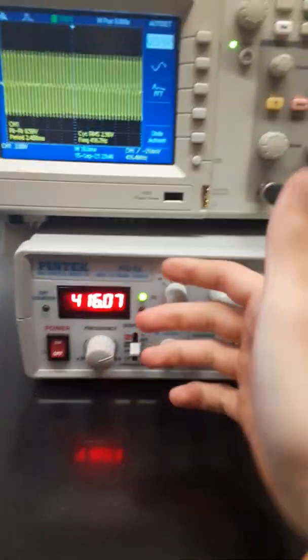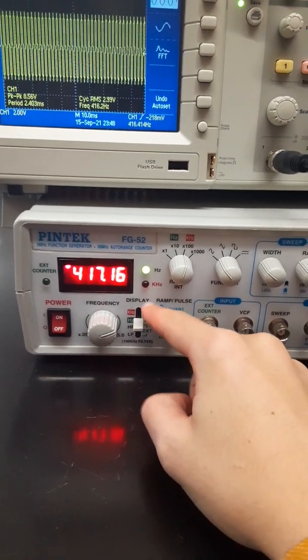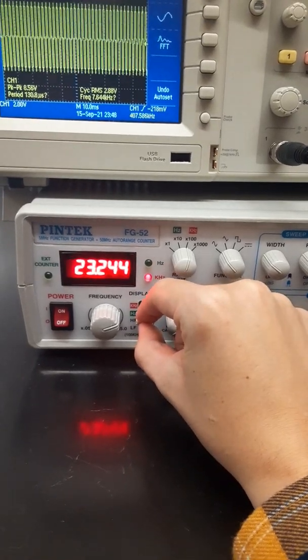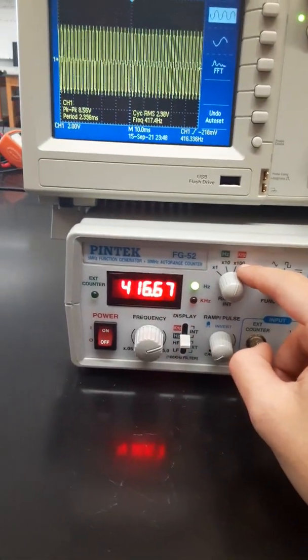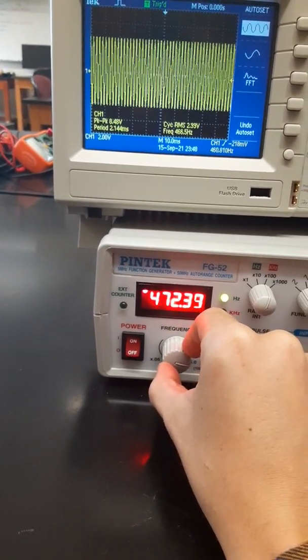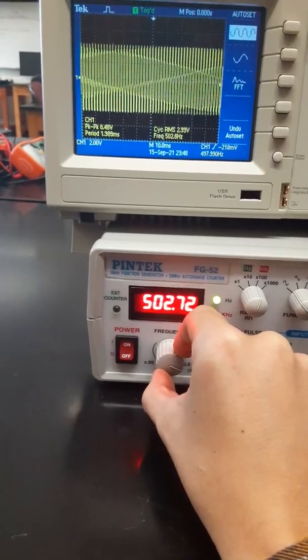So first of all, with units, you can see that this light is turned on, so the units are in hertz. If we need to change that, which we will later, we can go ahead and just flip this, and you see the units change. And we have a multiplicity of times 100, so we're going to go ahead and change this to 500 hertz. Really sensitive. Alright, that's good enough.